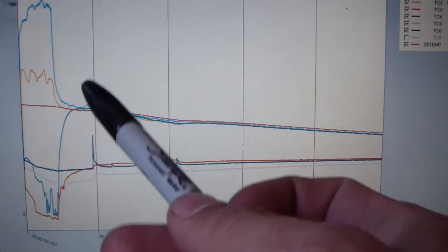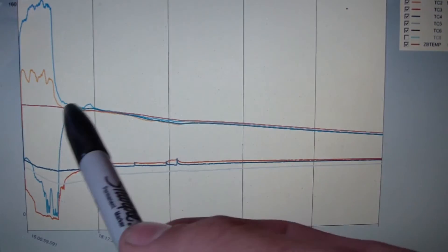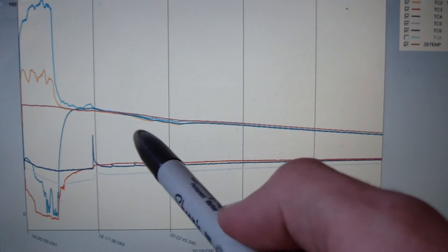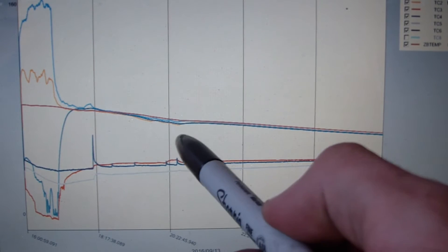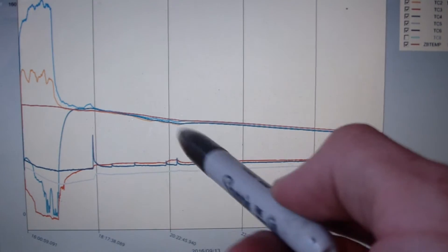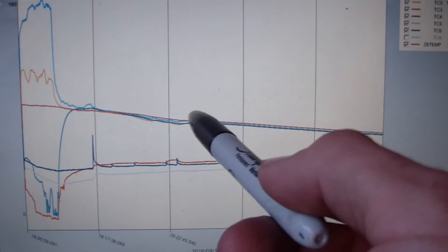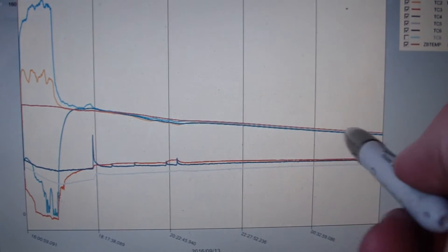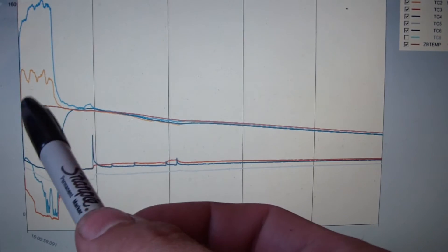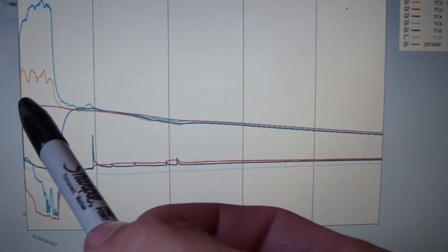There's a general downward trend that you see here. That's the Zoom box temperature and also the thermocouple that's on the suction right before the compressor. Since it's out in ambient, even insulated, it obviously warms up a good bit.